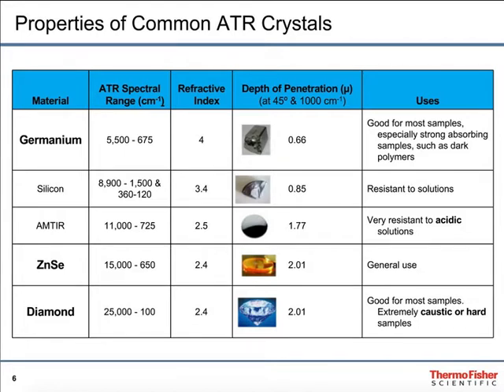However, diamond is also the most expensive. Zinc selenide has a very similar depth of penetration, but the crystal is much softer, and therefore it's not nearly as robust, and it has a slightly narrower spectral range. Germanium has the advantage of a very high index of refraction, which gives it a shallow depth of penetration. So for materials which are either highly absorbing or highly scattering, like carbon black rubbers, those materials are very easy to run on germanium, where the spectra on other materials would not be as good.